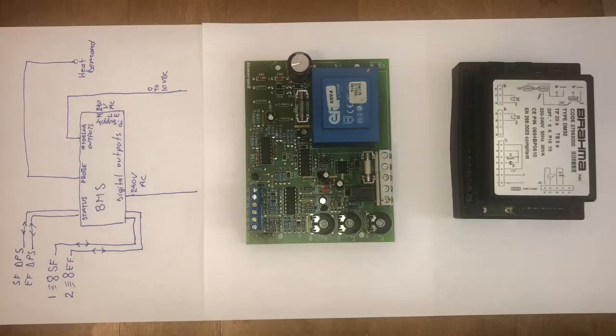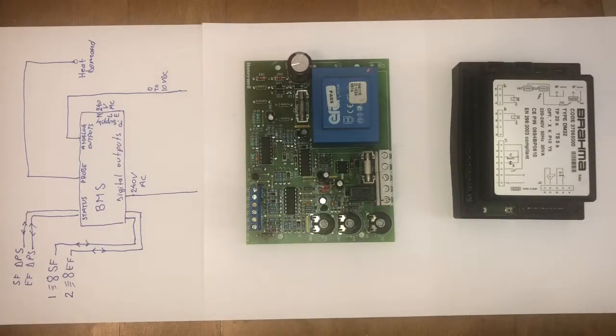You turn up to the store for the first time, and one guy will show you where the air handling unit is, and bang, you find yourself in front of one of these systems. Now, as a gas engineer and control engineer, you have to understand that there are safety features. I'm not talking about the ionization probe, because that will be the last thing to think about. That will automatically send incorrect information to the Brahma, which will cut the flame anyway. But I'm not talking about this. I'm just talking about the initiation protocol.